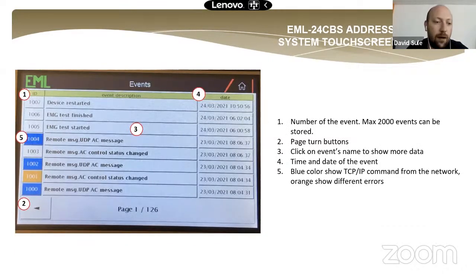The panel can contain the last 2000 events of the system. So in the event section, we can read these events. Different colors mean different events. The blue color shows the events came from other TCP IP or other RS-485 networked slave panels in the system. The orange color means something error.